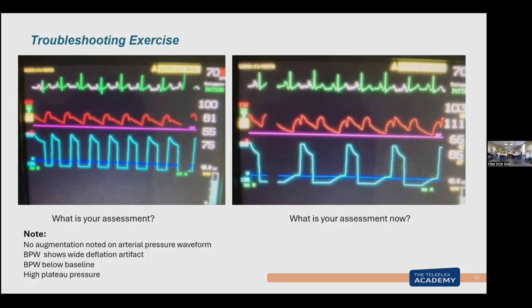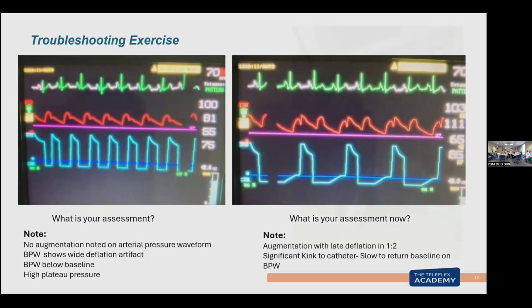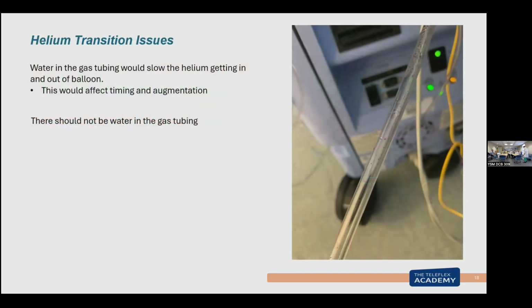Then what we did with this one, I thought I've got to get something to the balloon so we can troubleshoot this. We went to 1 to 2. Now I've got more time to allow the helium to get past whatever obstruction is there. It gets back to baseline. This starts to look a little more normal. I've got some augmentation in, but I have late deflation. That's because it's taking so much time to get back out. So now I need to try and decrease my volume. We may have to replace this balloon. But that's the difference that you can see with that. We call that a slow balloon, trying to get the helium in and out.